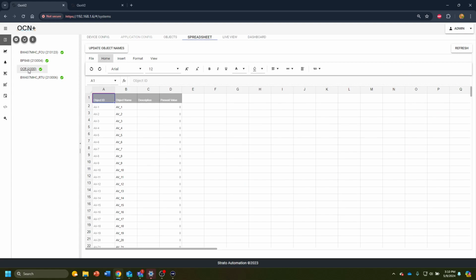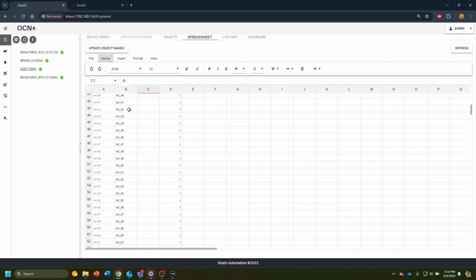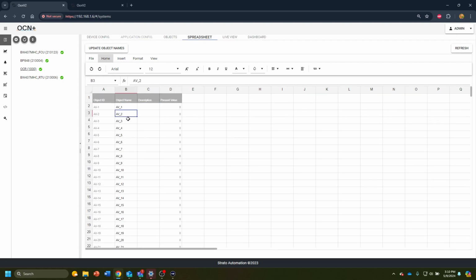Now for the spreadsheet tab here, I'm going to go over to my OCR, my BACnet router. That's currently the only device that this feature has any use case for, but what it allows me to do is edit the object name and description for these values, and then hit update object names, and it's going to save that to the device. So if I want to create custom programming, this would be useful rather than just have AV1, AV2, etc. I can actually name these points for what they are associated with, like base temp, cooling demand, you name it, whether it's based on points from a different device or just your standard points that you want to name.